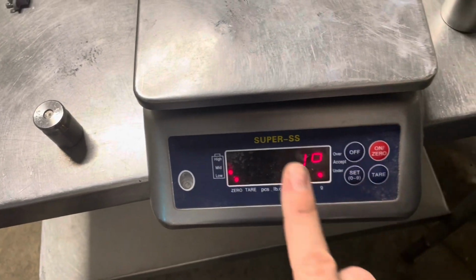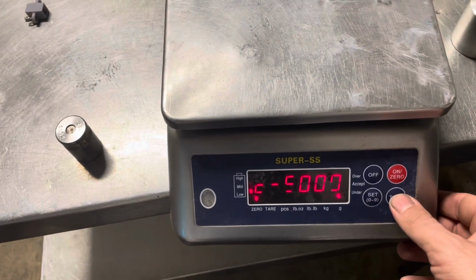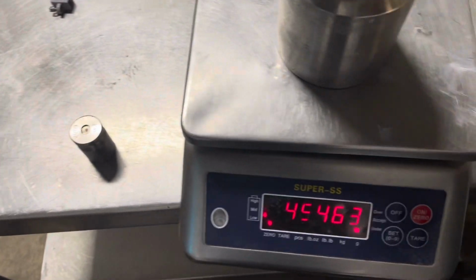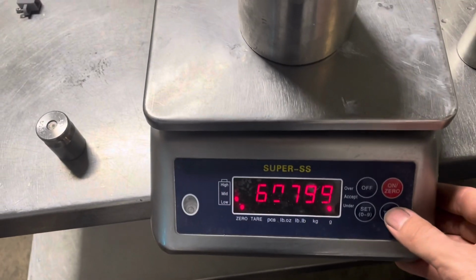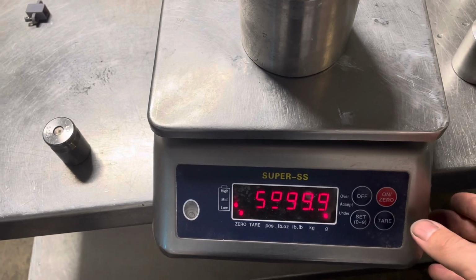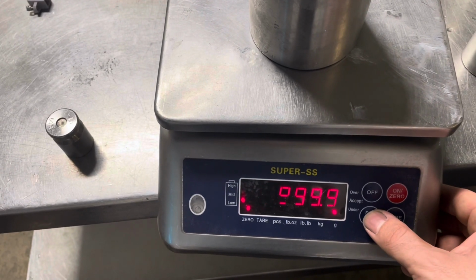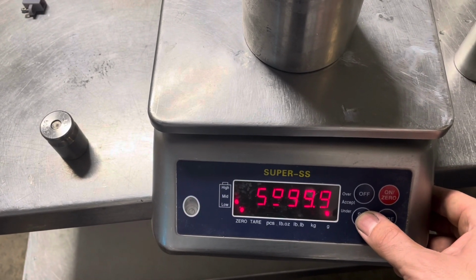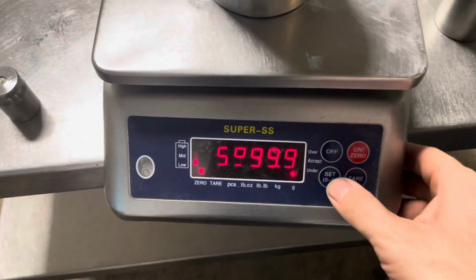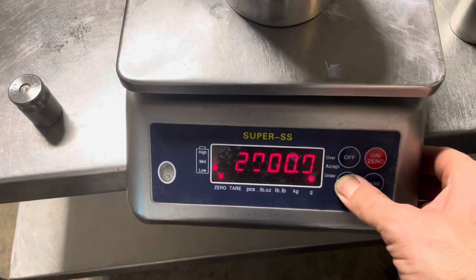Now again, I wanted to show the difference between a single point calibration to a linear calibration, and that's multiple points. Because the scale still has life. If you do a linear calibration, it'll be accurate. If you do a single point, it will not be accurate. And you can change the weights to calibrate on the scale. Say if you don't have the 6 kgs or a 15 kgs or whatever the scale needs. You can also do substitution weights, but that's neither here nor there. It's for a different video altogether.